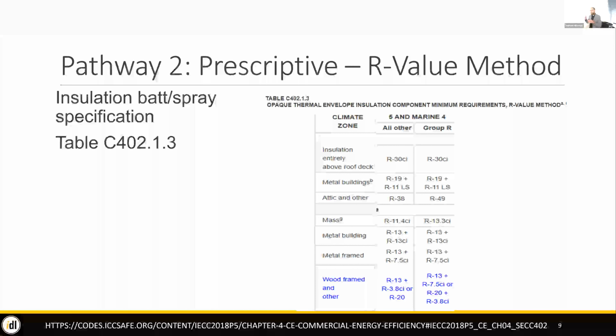You've got metal, and if the metal is hitting both the outside and the inside, the heat transfer going through it is going to be enormous. So that's why they have that extra specification of continuous insulation. A mass building would be like CMUs, bricks, that requires continuous insulation. Whereas if you see in the metal building, for our climate zone 5, parts of Idaho are climate zone 6, but we're mostly 5, you see the R13 plus R13 CI. So that means you need an R13 batt going in between the metal studs, and in addition to that, you need another R13 continuous that's going either outside or inside of the studs. So it's going across those.